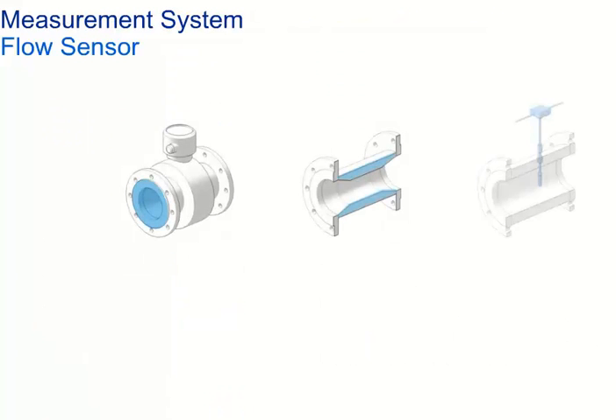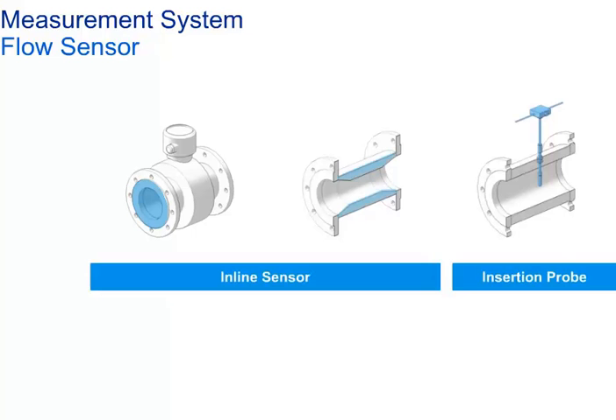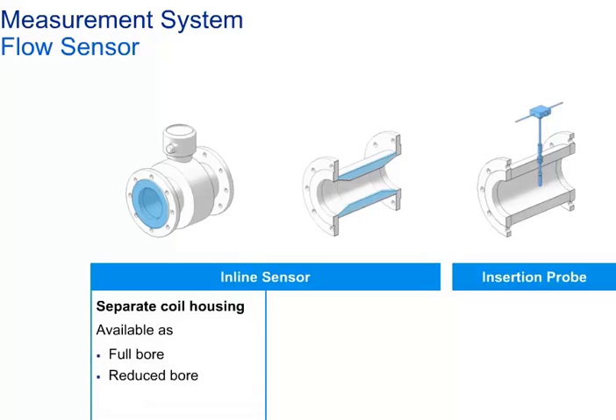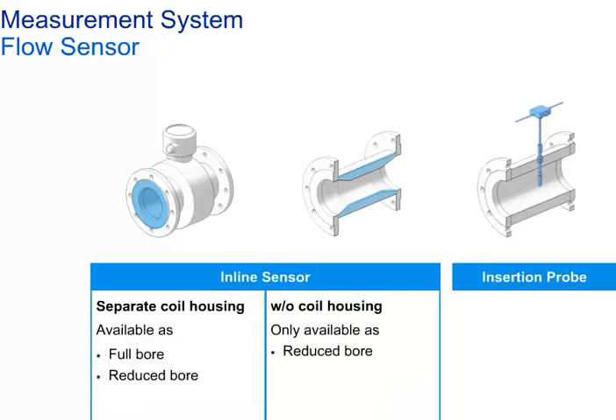There are different constructions of the sensor body available. In general, there are two main types: inline and probe sensors. With inline sensors, the coils can be in a separate housing outside the meter tube, or they can be inside the meter tube. There are also insertion types which are inserted into the flow conduit; due to this insertion construction, there is a reduction in the cross-section area of the bore — we have reduced and full bores. With insertion probes, the sensor design is different from the inline types.